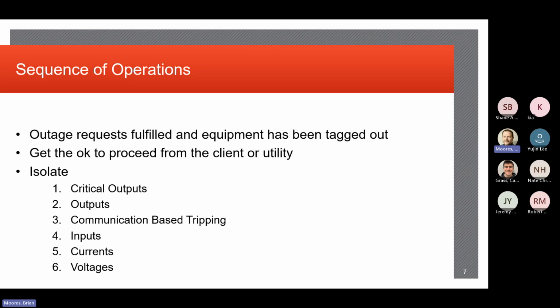If you think about a logic diagram, all your outputs are on the right-hand side, all your inputs are on the left-hand side, and all your logic is in the middle, right? If you look at it from left to right. So you start from right to left, essentially, to go through your isolation of those test switches. Get your outputs done so you're not worried about causing any trips.